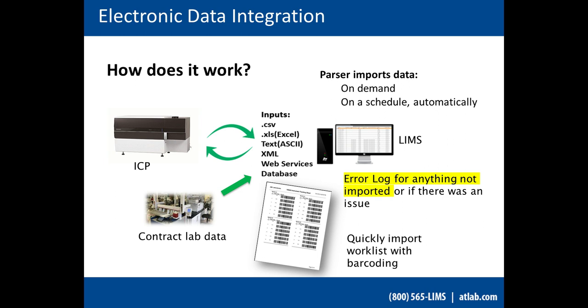On upload, you can perform data quality checking and create an error log if anything is found. Instruments typically output a number of file formats including comma-separated value (CSV), Excel, text/ASCII, XML, web services with an API, or database-to-database. The imports can be on demand or on a schedule, and you can also very quickly import data from contract testing laboratories into your LIMS.